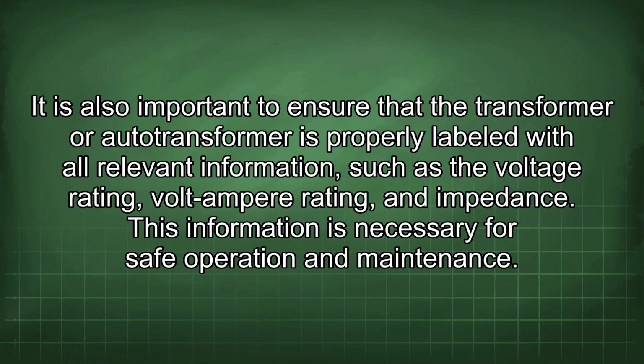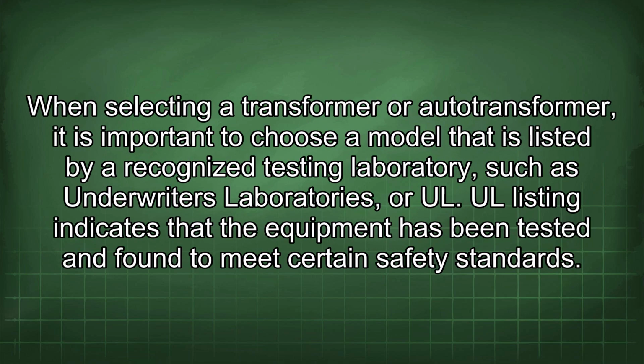It is also important to ensure that the transformer or autotransformer is properly labeled with all relevant information, such as the voltage rating, volt-ampere rating, and impedance. This information is necessary for safe operation and maintenance. When selecting a transformer or autotransformer, it is important to choose a model that is listed by a recognized testing laboratory, such as Underwriters Laboratories, or UL. UL listing indicates that the equipment has been tested and found to meet certain safety standards.